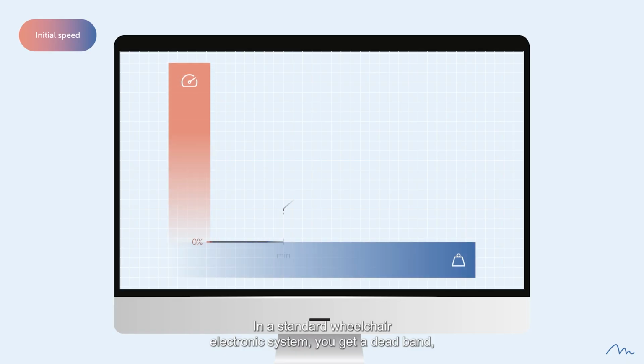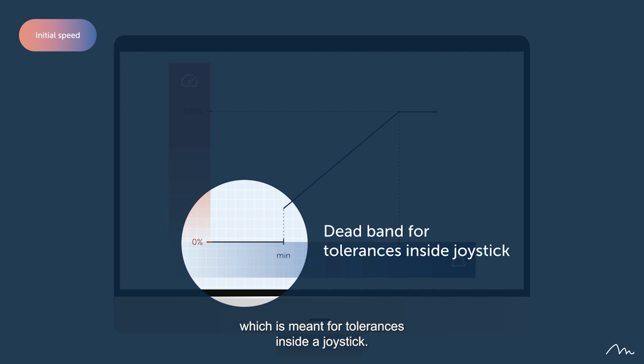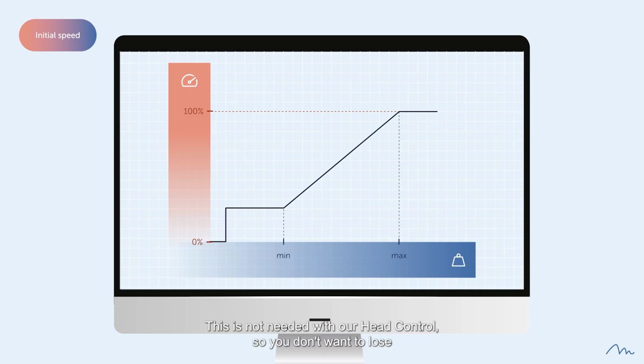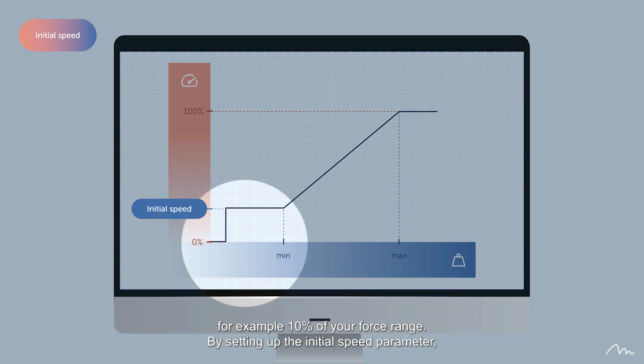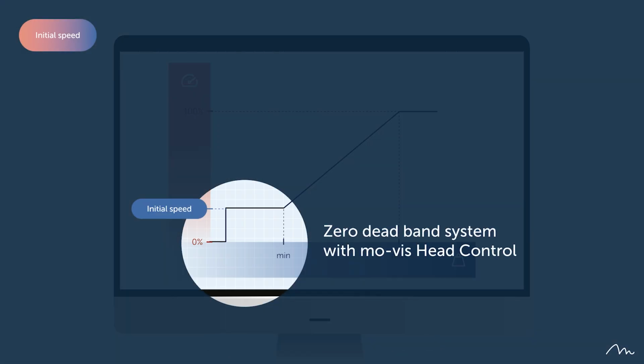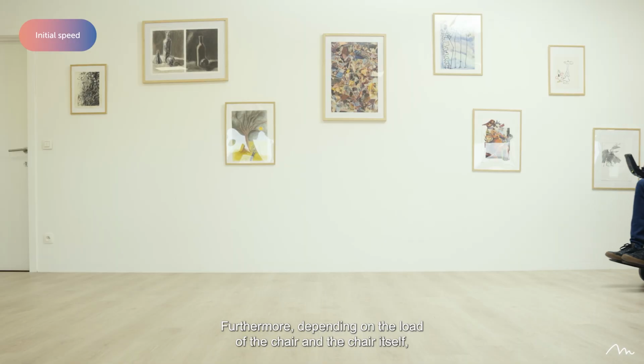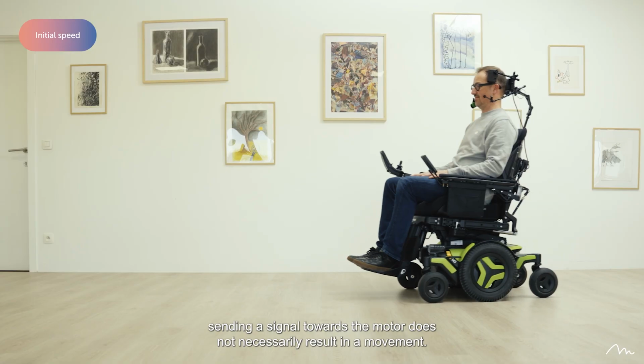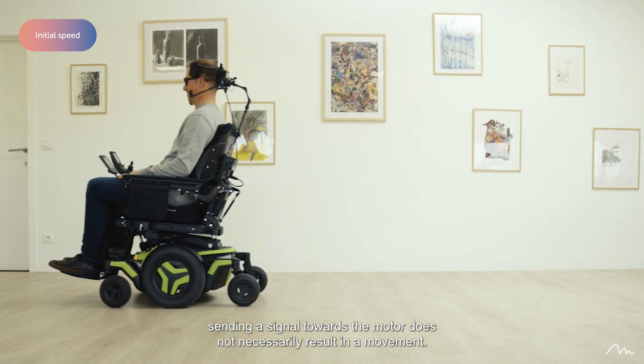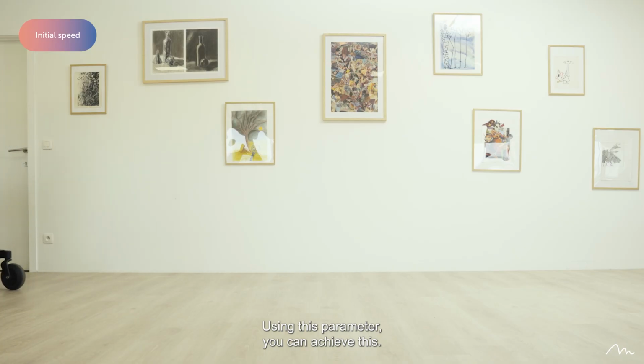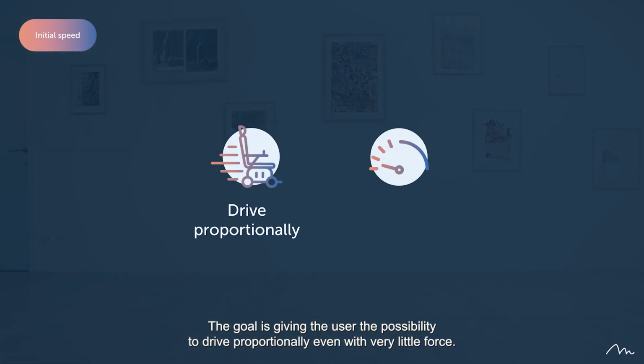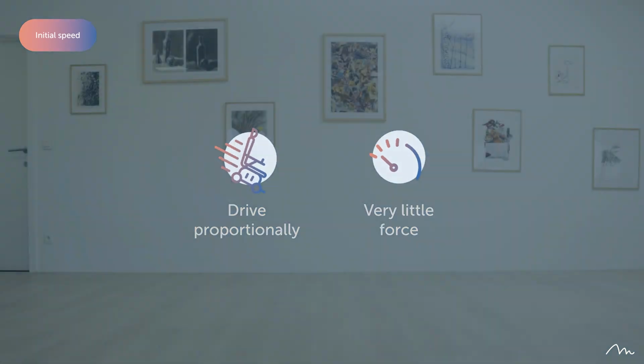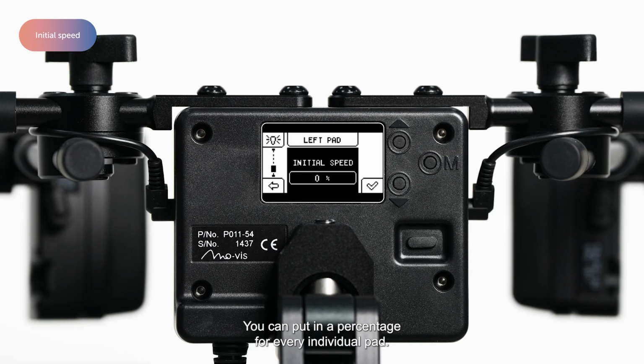In a standard wheelchair electronic system, you get a deadband, which is meant for tolerances inside a joystick. This is not needed with our head control. So you don't want to lose, for example, 10% of your force range. By setting up the initial speed parameter, you can create a zero deadband system. Furthermore, depending on the load of the chair and the chair itself, sending a signal towards the motor does not necessarily result in a movement. Using this parameter, you can achieve this. The goal is giving the user the possibility to drive proportionally, even with very little force. You can put in a percentage for every individual pad. Don't forget to save by long pressing the menu button.